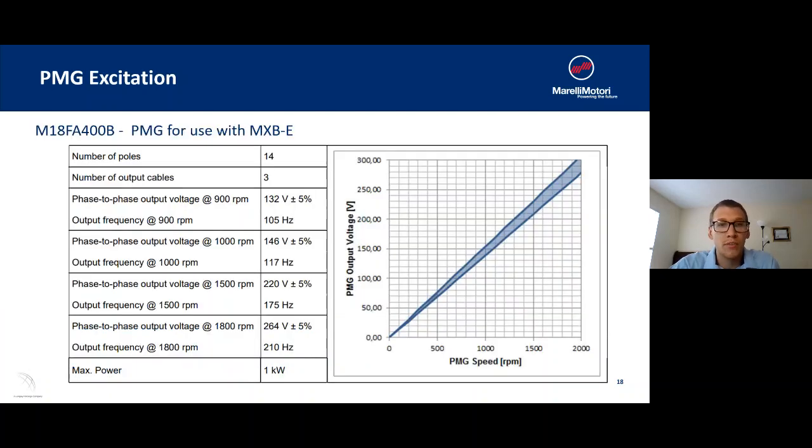So for example of a PMG that we use, this is one that we would use for our MXBE series. It's a 14-pole PMG with three-phase output. Most US applications are operating at 1800 RPM, so we'll look down there. You're going to see a 264 volt, 210 hertz output that's around 1 kW. And that's what's going to be pushed into the AVR to power this system.